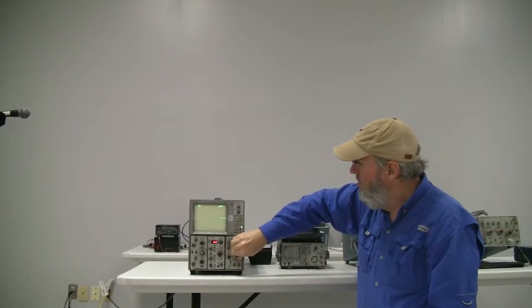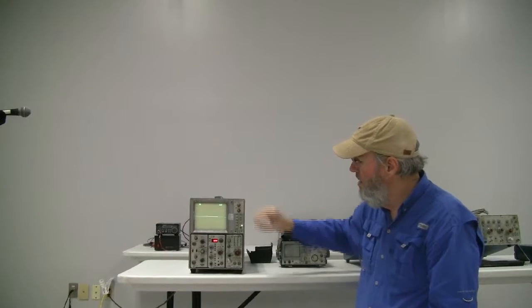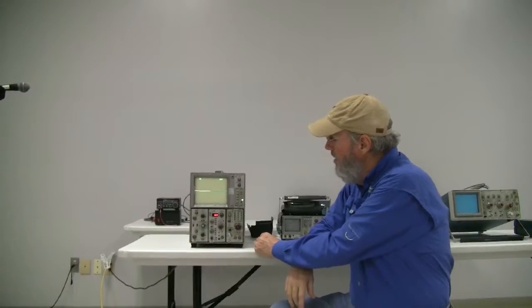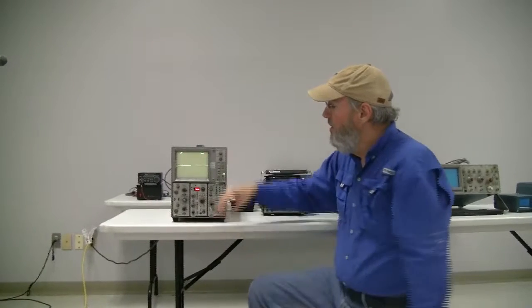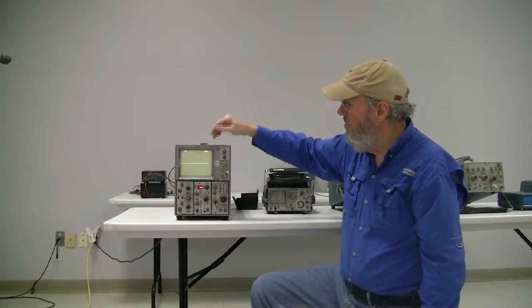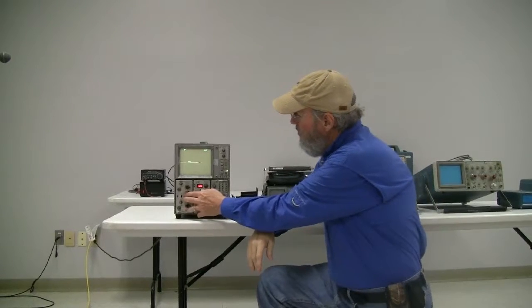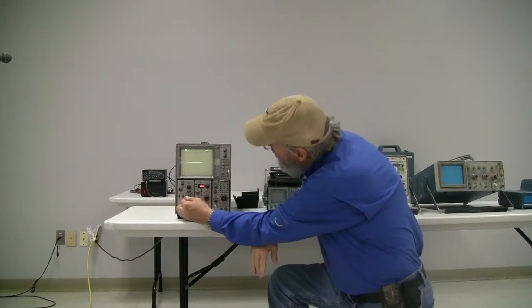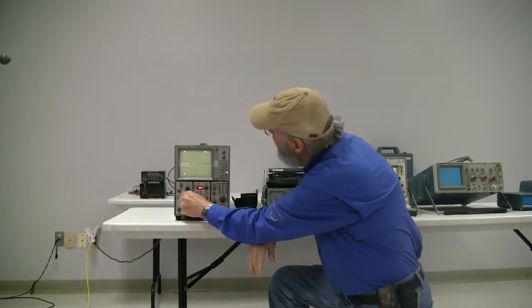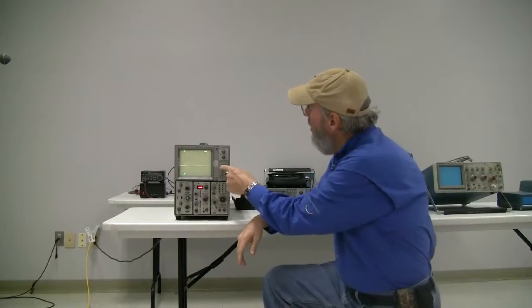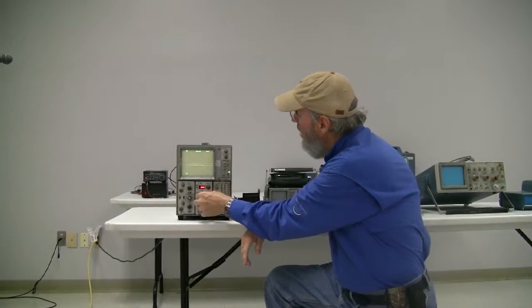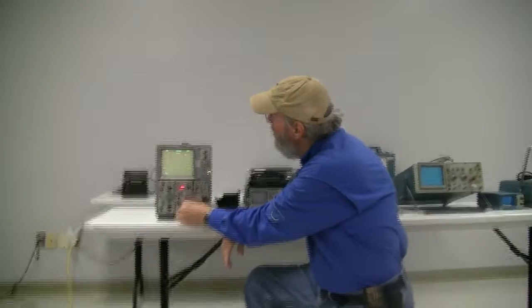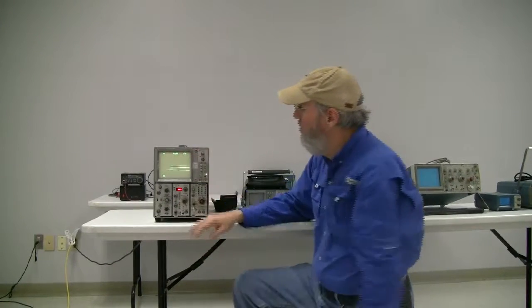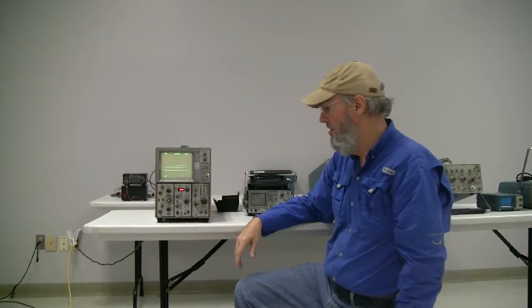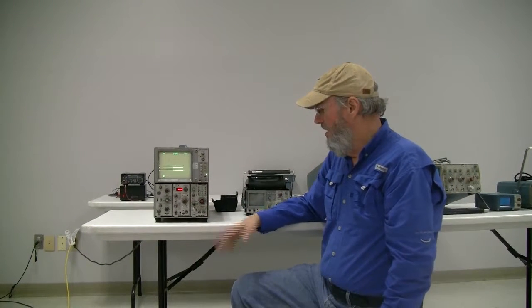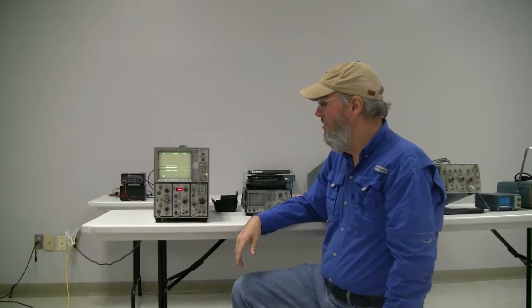Now, briefly about the actual units in this scope. This is a dual time base unit. It will actually show you a slow sweep alternated with a fast sweep. The left plug-in unit that's in there is a dual trace, meaning that I can switch in and have 2 traces from that one channel. I can also switch in and add a trace from the right side for a total of 3. You can put a dual trace plug-in here and have 4 traces. That's the main set of configurations for standard oscilloscope use.